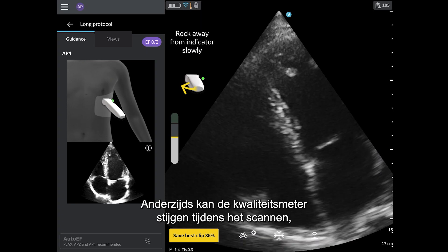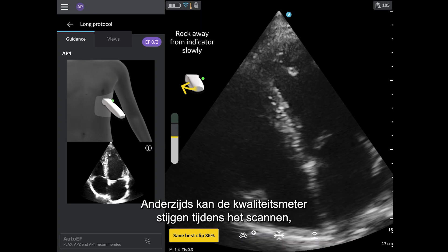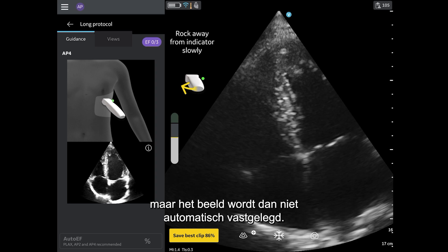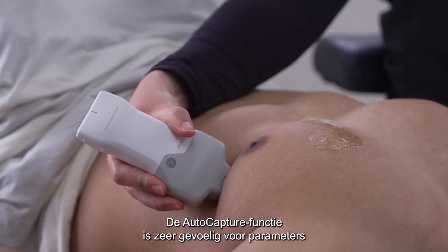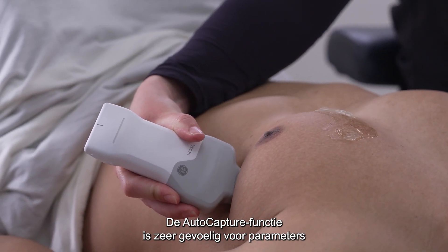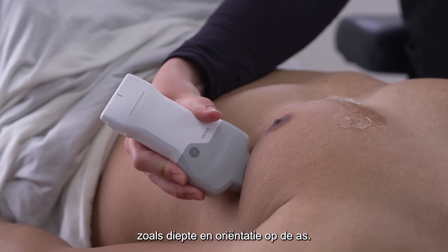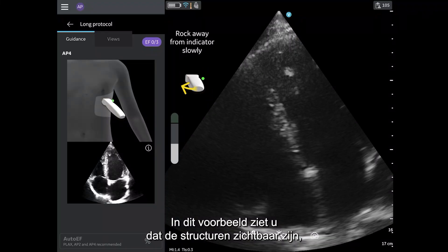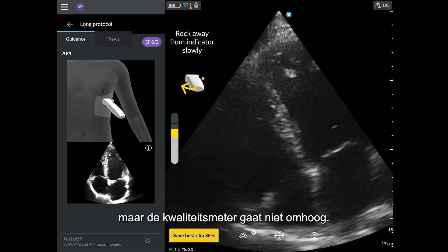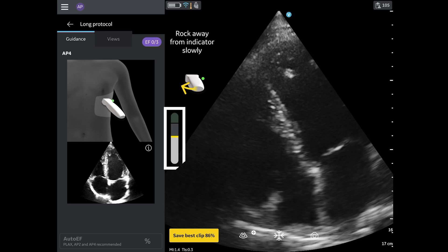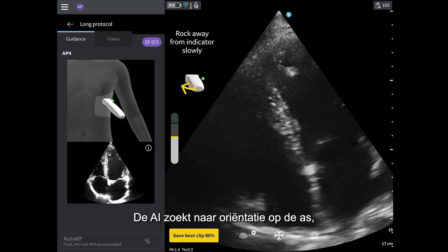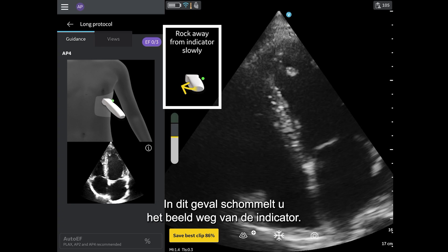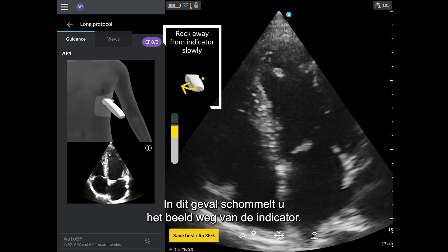Two, sometimes when scanning, the quality meter will rise and the image looks like the reference image, but the image is not auto-capturing. The auto-capture feature is highly sensitive to parameters such as depth and on-axis orientation. In this example, you can see that the structures are visible, but the quality meter is not going up. The AI is looking for on-axis orientation, which can be achieved by following the prescriptive guidance, rocking away from the indicator in this case.